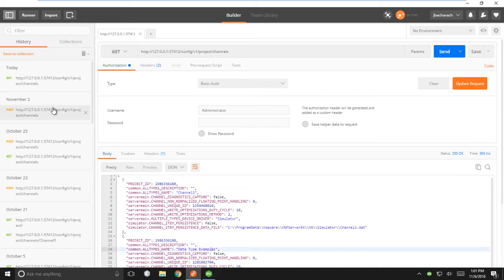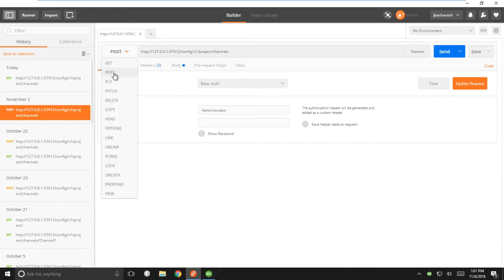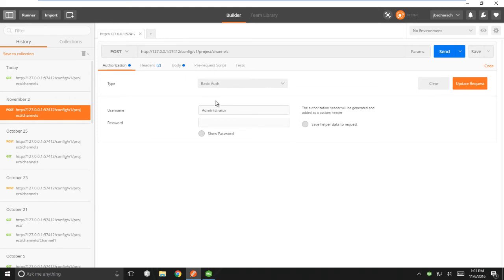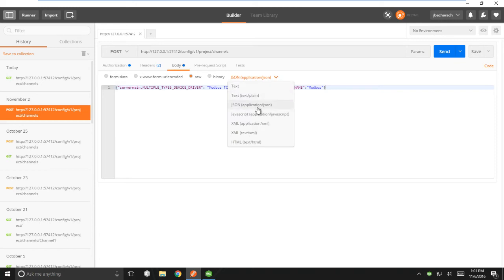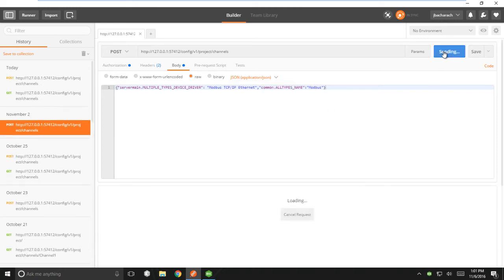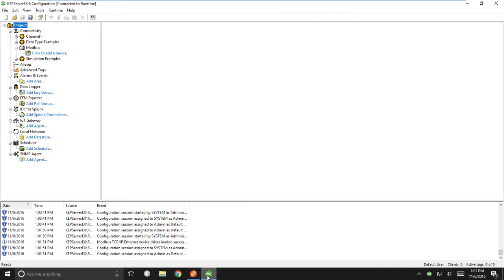The next command we're going to do is a Post. So we're going to select Post from the drop-down menu, and we're targeting the same URL with the same authentication settings. But this time, we're going to add a body, and we're going to add JSON in the body using a raw JSON format. That's going to create a Modbus TCP IP channel with the name Modbus. If I send this to the server, it will create a channel of that device type and that name. If I look at my server, I can see that that channel was created.